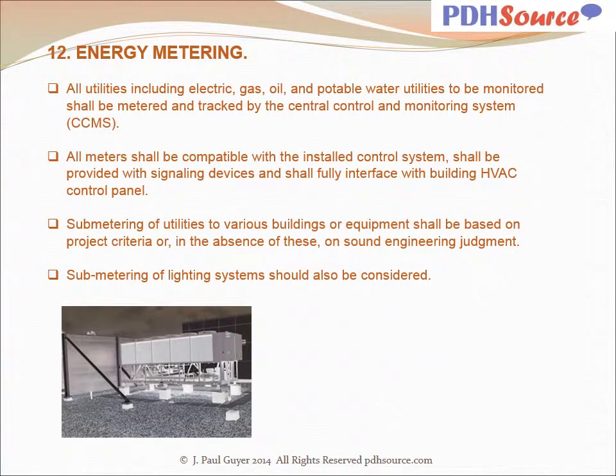All utilities, including electric, gas, oil, and potable water utilities to be monitored, shall be metered and tracked by the Central Control and Monitoring System, CCMS. All meters shall be compatible with the installed control system, shall be provided with signaling devices, and shall fully interface with the building HVAC control panel. Submetering of utilities to various buildings or equipment shall be based on project criteria, or in the absence of these, on sound engineering judgment. Submetering of lighting systems shall also be considered.